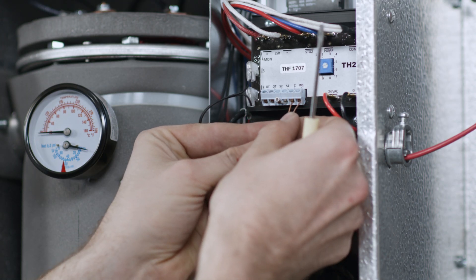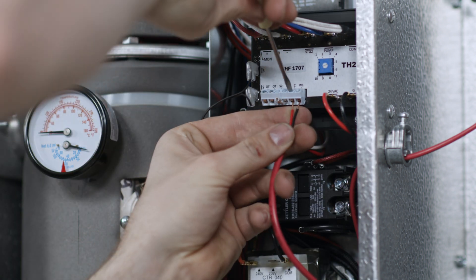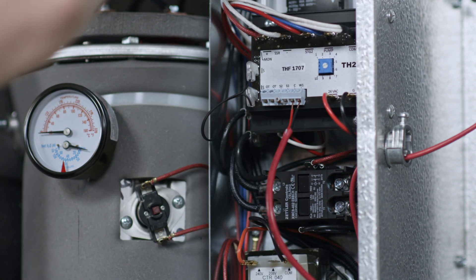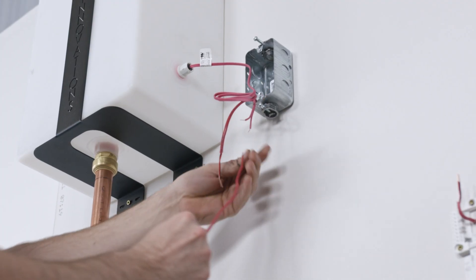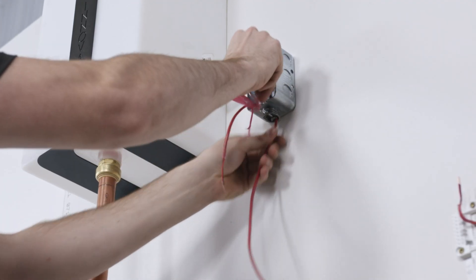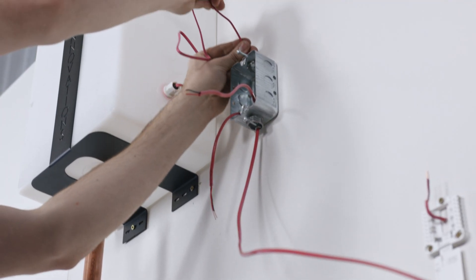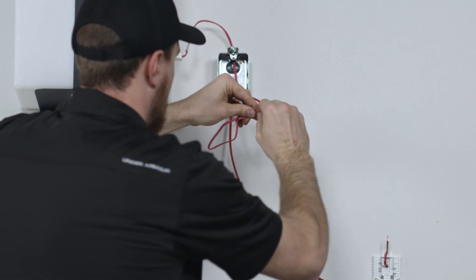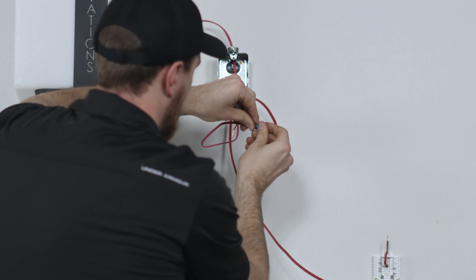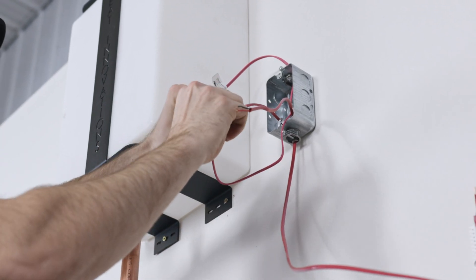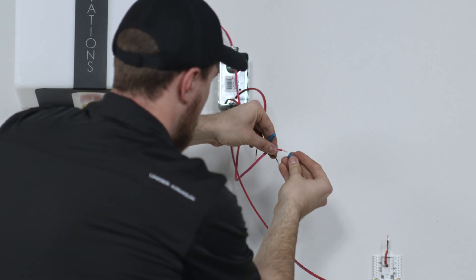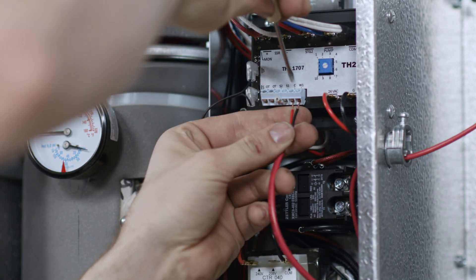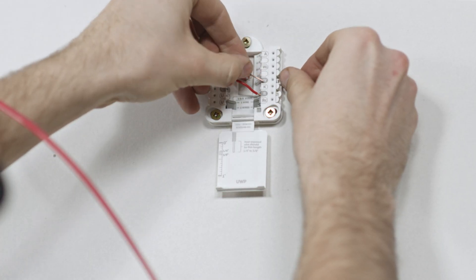On the boiler, you will need to connect your low water cutoff switch and thermostat to the W1 and C terminals. Take one wire from W1 and connect it to the first wire on the LWCS. Then, take the second wire on the LWCS and run it to R on the thermostat. Then, run a wire from C in the boiler to W in the thermostat.